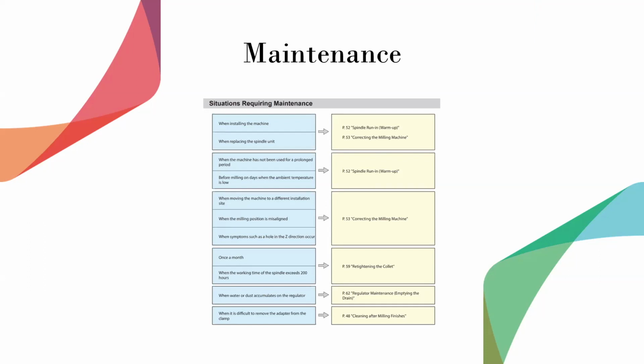When you see that sort of thing in a lab and there's a lot of work to do, it can be easy to say it's shifted a little bit to one side, but what's the big deal? Let's just run it. You've got to pay attention to those things on any milling machine. If you ignore them, or try to brush them under the rug and hope that it goes away, it's probably not going to go away, and it'll probably just make the problem worse. Like you said, down the road, the next puck you put in, instead of milling one unit out of the center, you've nested the whole thing. As it gets to the perimeter, since it's shifted to one side or the other, you're milling into the puck holder, damaging it, breaking tools, having a bad day. It may be okay for this one run, but it's going to come back to haunt you if you don't get it squared away now.